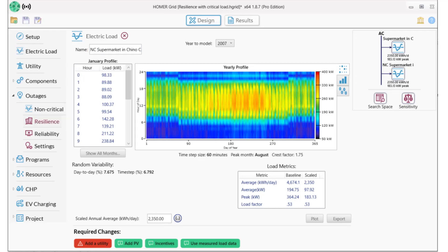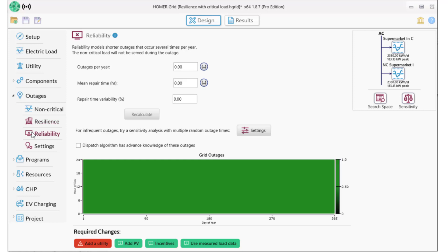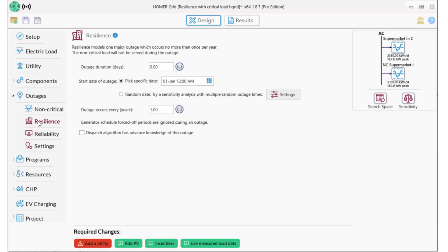Let's set up the rest of the outages section while we're here. Homer Grid offers two types of outage modeling: resilience, which allows you to model long but infrequent outages, and reliability, which are shorter outages that may occur multiple times in a given year. We're going to model resilience, and I'll set this up for outages that are five days long.